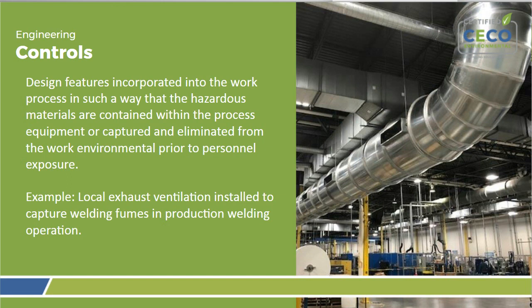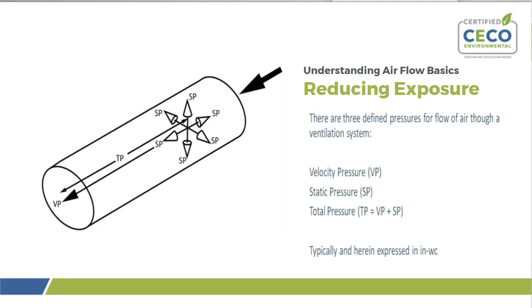Now, in order to implement engineering controls, we first have to have an understanding of some airflow principles. Understanding airflow is key to reducing employee exposure to airborne hazards. The flow of air between 2 points is due to a pressure difference between the 2 points. There are 3 defined pressures for flow of air through a ventilation system. We have velocity pressure, VP, static pressure, SP, and total pressure, TP, which is the sum of our velocity pressure and static pressure. Typically, these are measured in inches of water column.